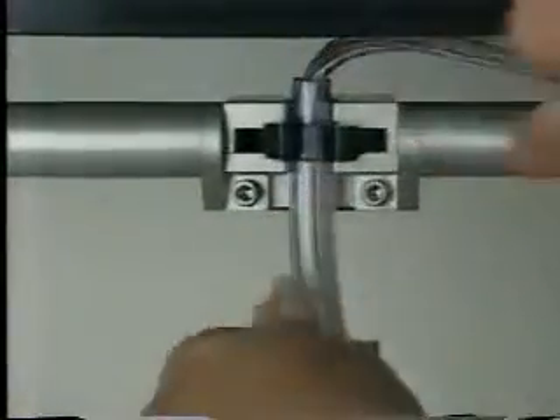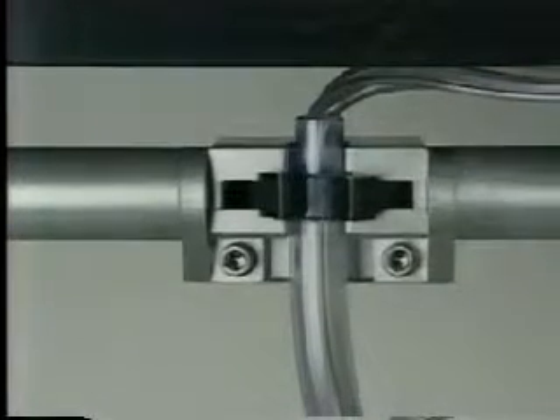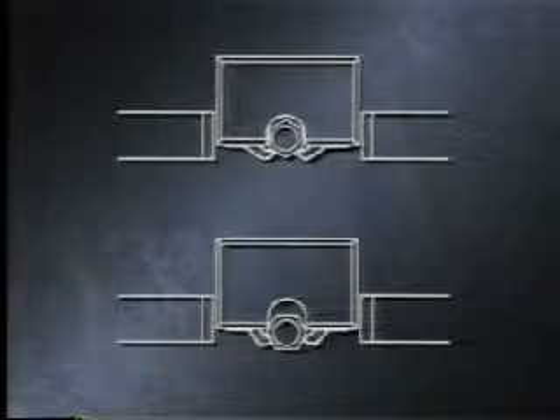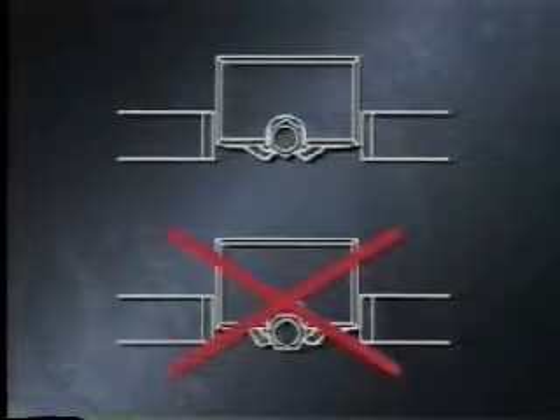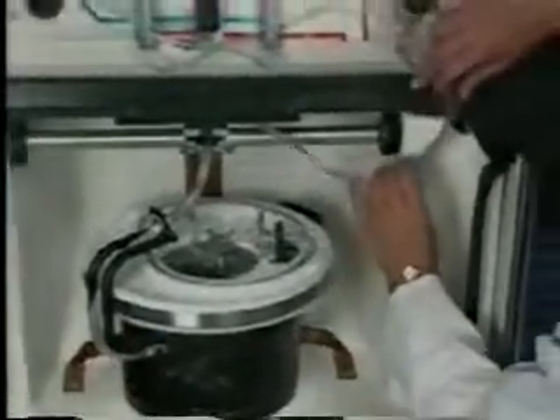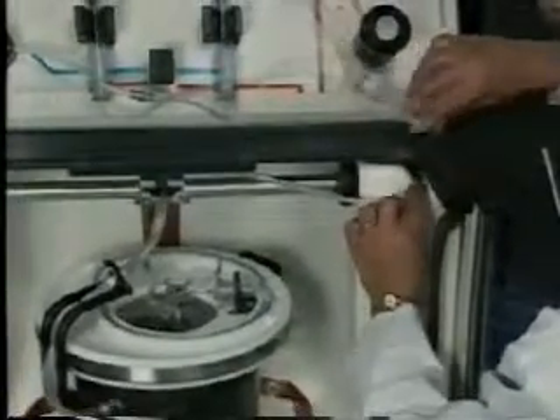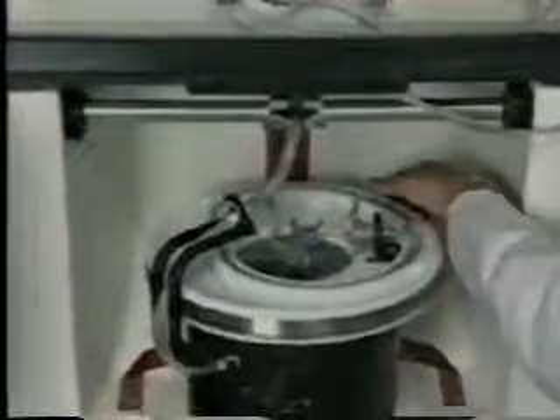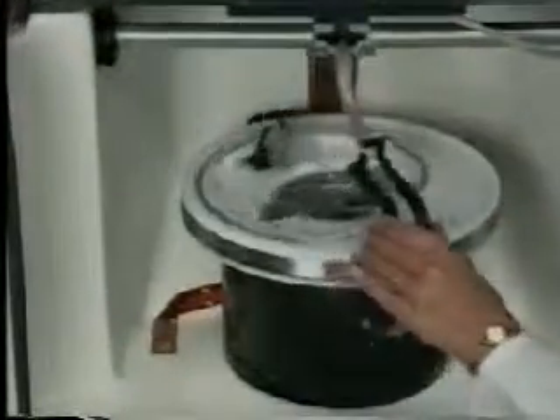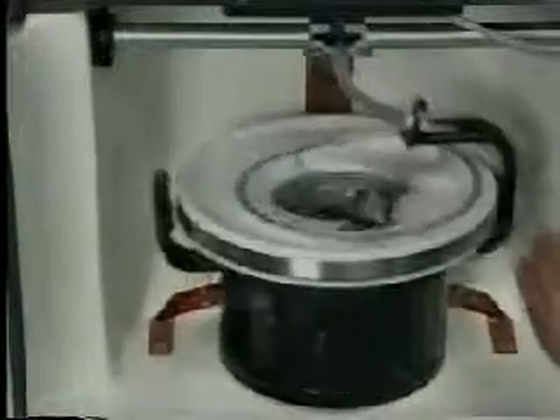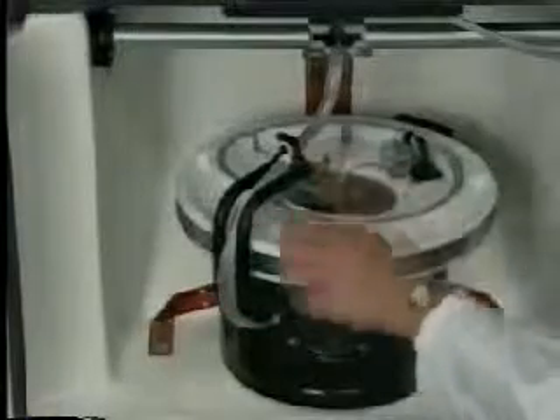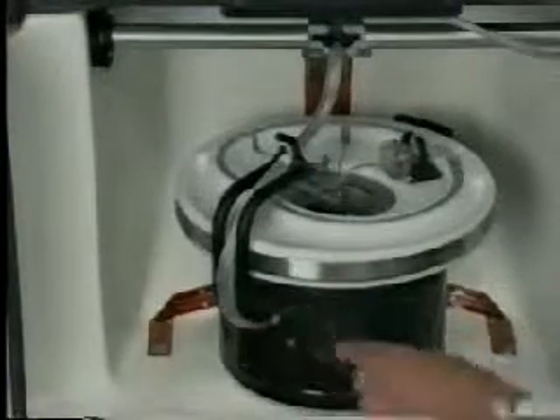Place the upper collar in the upper collar holder. Visually check that it is installed properly as shown by this diagram. Inspect all lines to ensure that they are not kinked. Floss the tubing into the exit slot. Rotate the centrifuge in a clockwise direction several times to ensure that the tubing is secure and will not twist. Both the upper and lower bearings should also remain in place. Close the centrifuge door and cover. Now let's take a look at this process from beginning to end.